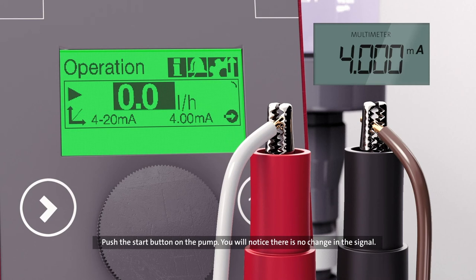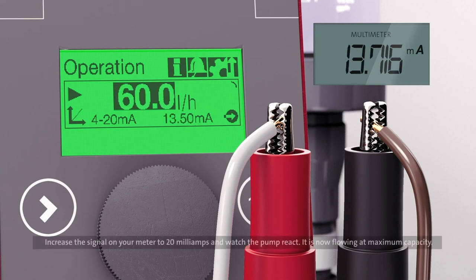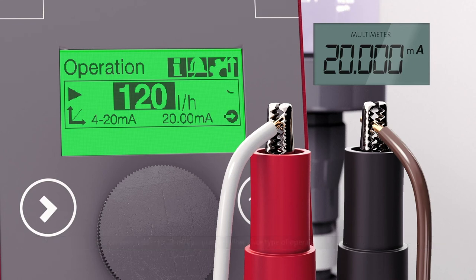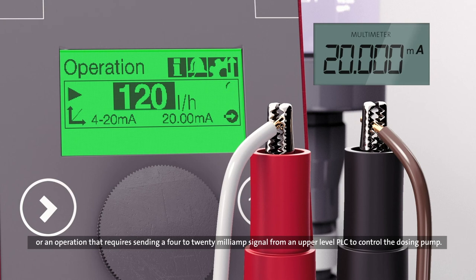You will notice there is no change in the signal. Increase the signal on your meter to 20 milliamps and watch the pump react. It is now flowing at maximum capacity. This is very similar to a flow paced type of operation, or an operation that requires sending a 4 to 20 milliamp signal from an upper level PLC to control the dosing pump.